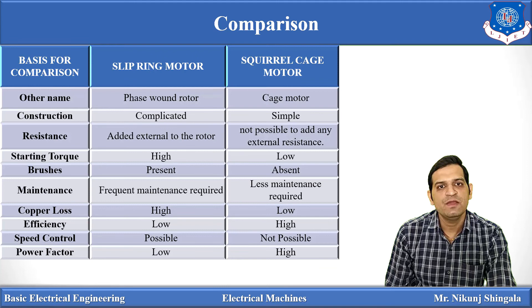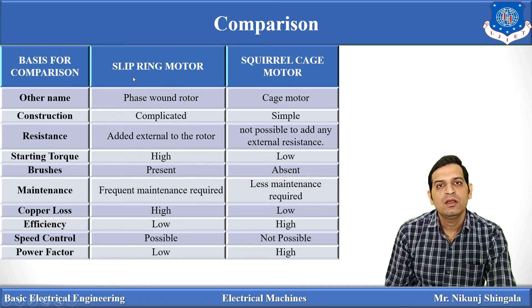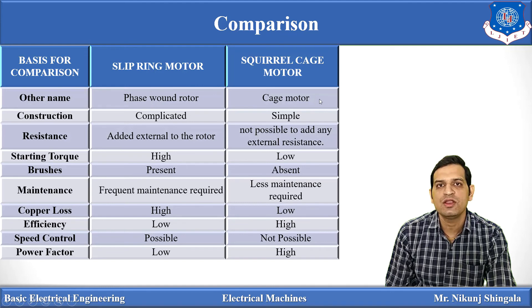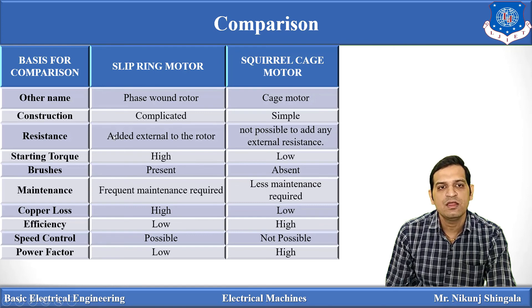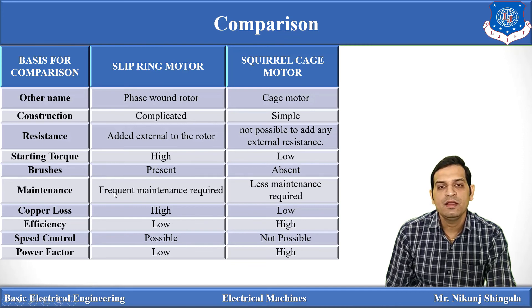Now let us look at the comparison between slip ring motor and squirrel cage motor. Three-phase induction motors are classified based on the type of rotor used. The slip ring motor uses slip ring rotor (phase-wound type); the squirrel cage motor uses cage type rotor. Construction of the slip ring motor is complicated due to windings; the squirrel cage motor has simple construction using copper bars. External resistance can be added in the slip ring motor but not in the squirrel cage motor. Starting torque is very high and variable for slip ring, and low for squirrel cage. Brushes are present in slip ring motor and absent in squirrel cage. Frequent maintenance is required for slip ring motor; less maintenance is needed for squirrel cage.